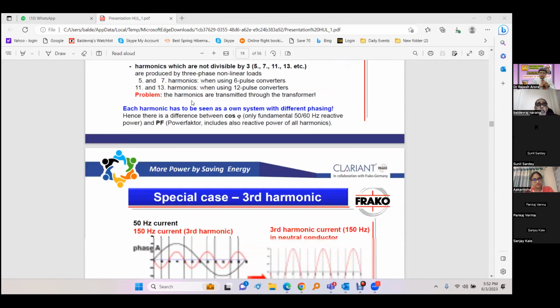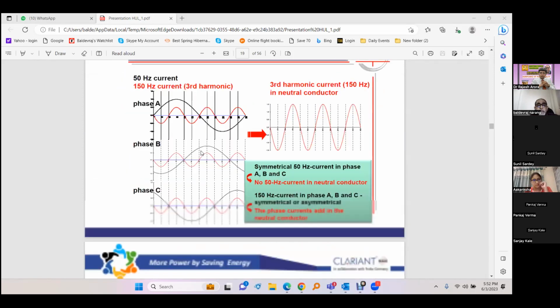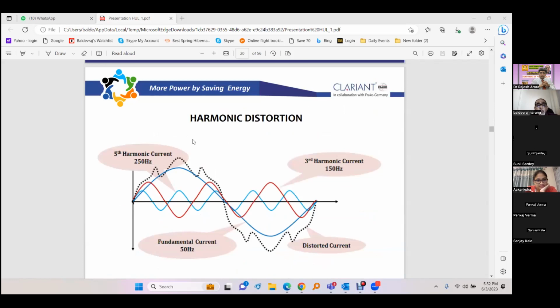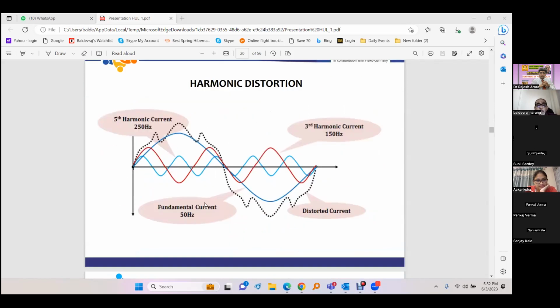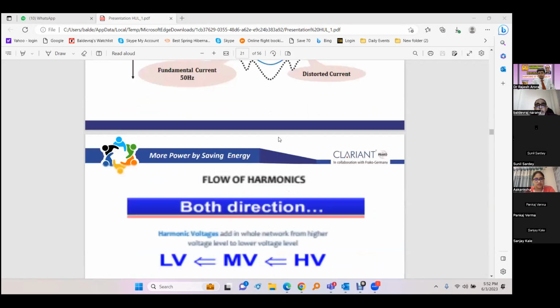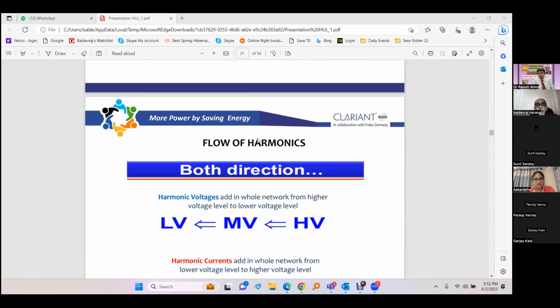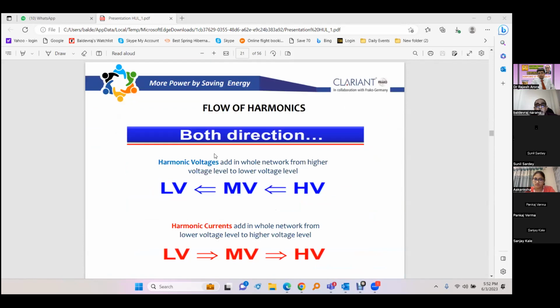So this is how a third harmonic is shown here. And here we have shown how the harmonic distortion occurs. We have here the third harmonic, fifth harmonic, fundamental current, and then the resultant current is shown in dotted line. So this is how the resultant current will look. So we have this flow of harmonics.